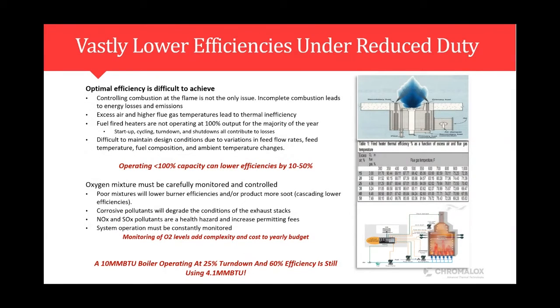And then we also talk about operational efficiencies. So we know the fuel-fired systems do not operate at peak efficiency across all cases. Typically, these systems have about a 4 to 1 or possibly up to a 10 to 1 turn down capability. But by turning down these systems, you have to increase your excess air percentage to make sure that you have full combustion. That excess air is pulling heat away to the flue, and it's also diluting the streams. So there's a lot of efficiency that's lost when you turn these systems down.